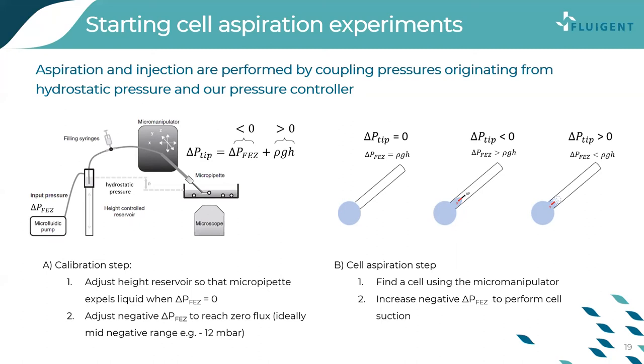This zero equilibrium should be obtained within the mid-negative range of our pressure controller — between zero and minus 25 millibar — ideally at minus 12 millibar, so that you have the highest level of control to either aspirate or inject the cell. Once the calibration step is performed, you can find the cell using the micromanipulator and play with the negative pressure to either aspirate or expel the cell or tissue. Feel free to ask questions at the end of the webinar.